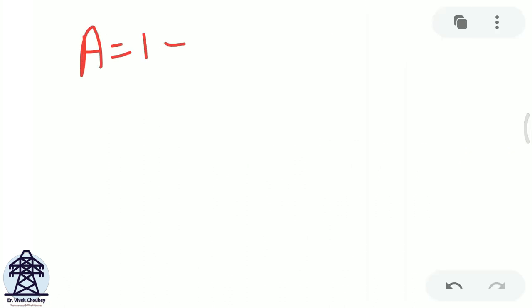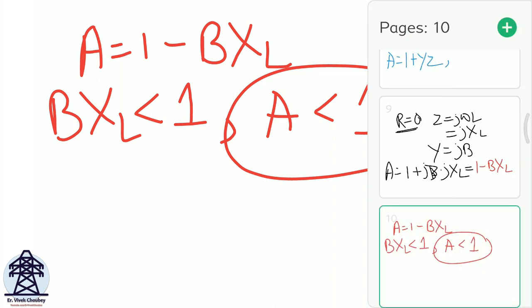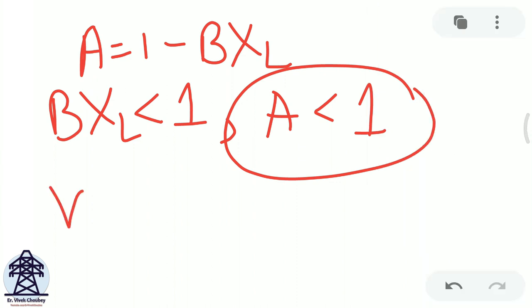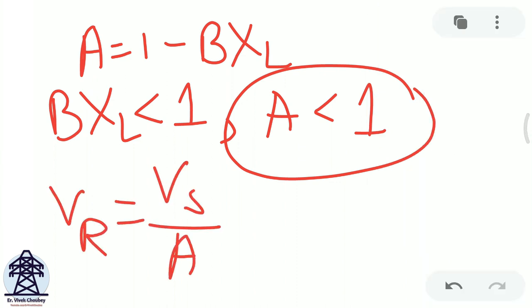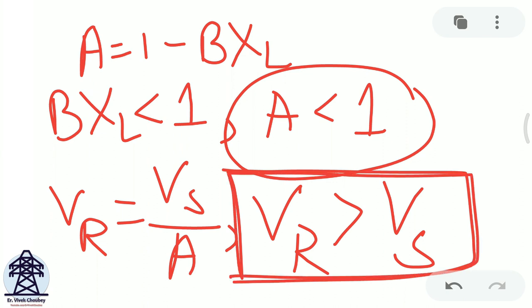Since B·XL is positive and less than 1 in a practical line, A = 1 − B·XL is less than 1. Since VR = VS / A and A < 1, VR is greater than VS. This is the Ferranti effect: under no-load or light-load conditions, the receiving end voltage exceeds the sending end voltage. The term (1 − B·XL) is always less than 1 in practice, which proves this mathematically.